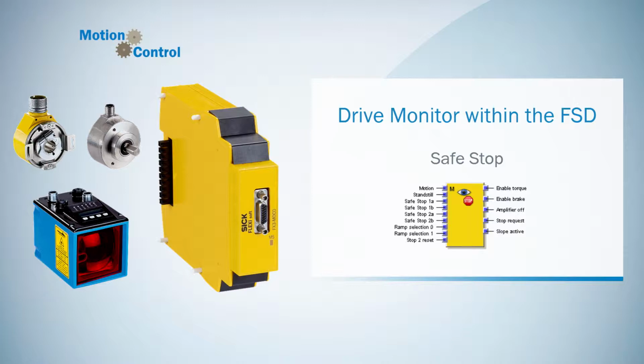This tutorial is about the motion function block Safe Stop, which is used to trigger and monitor the Safe Stop of a drive system. During this process, the drive must be shut down in a controlled manner. In this way, the brake torque of the drive can be used to bring the drive to a standstill in a shorter time than would be possible with an uncontrolled stop. As a stop ramp for the drive system is normally non-safe, the function block Safe Stop monitors the actual reduction in the speed down to standstill.